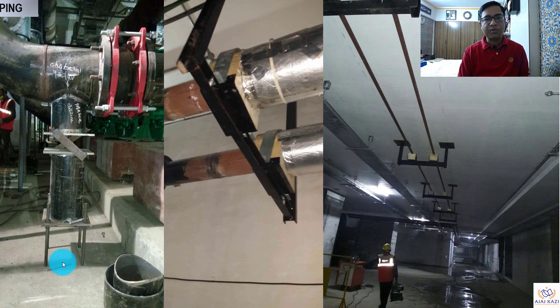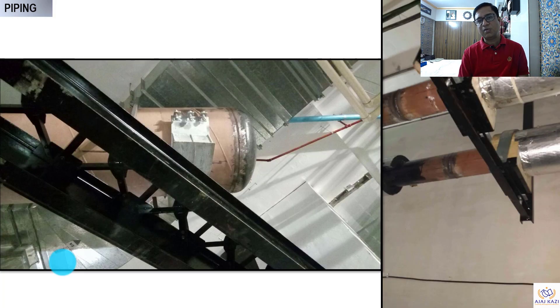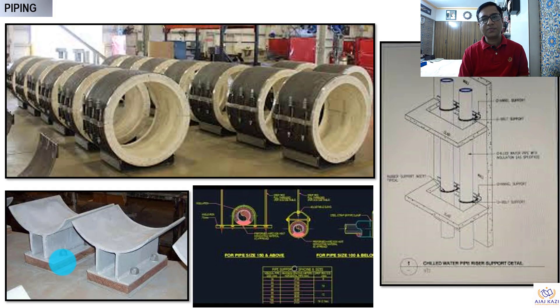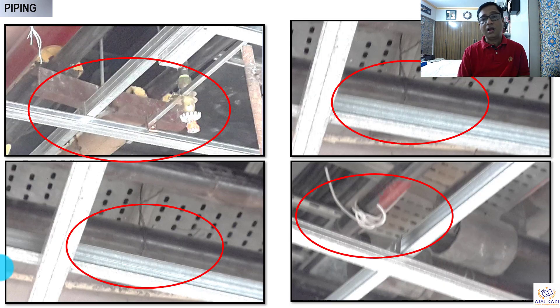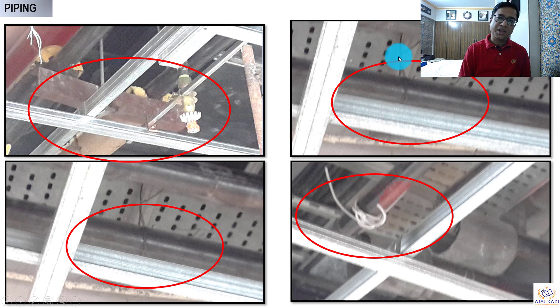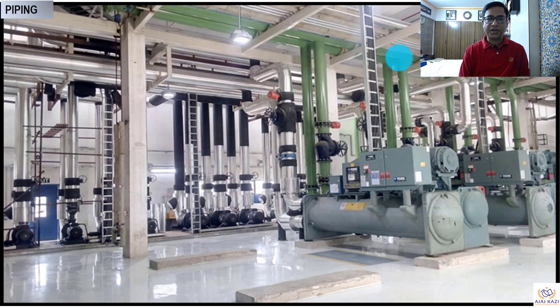There are different ways of supporting, but you should know what kind of supports are required. You can see cradle supports which take care of thermal expansion as well as horizontal movement due to fluid dynamics. On the other hand, some examples show bad practice — somebody putting a wire, somebody putting a metal wire — but this is not the way to support. I have shown both good and bad photographs so you can see how beautifully it can be done when done correctly.